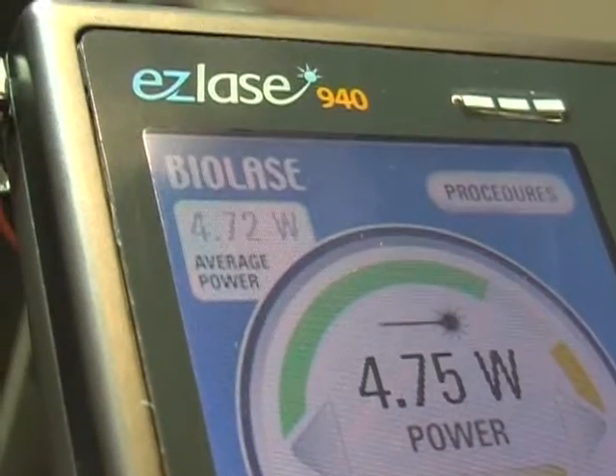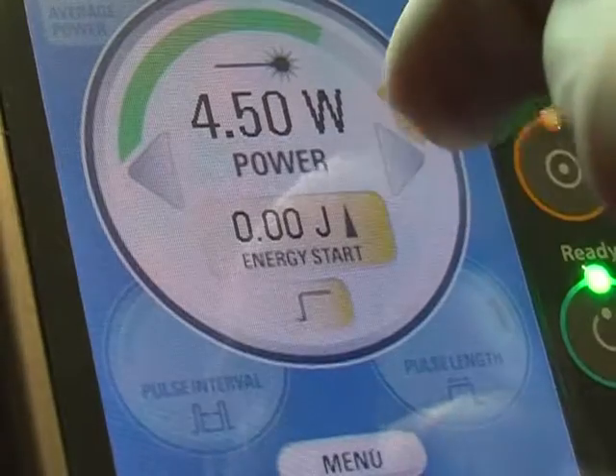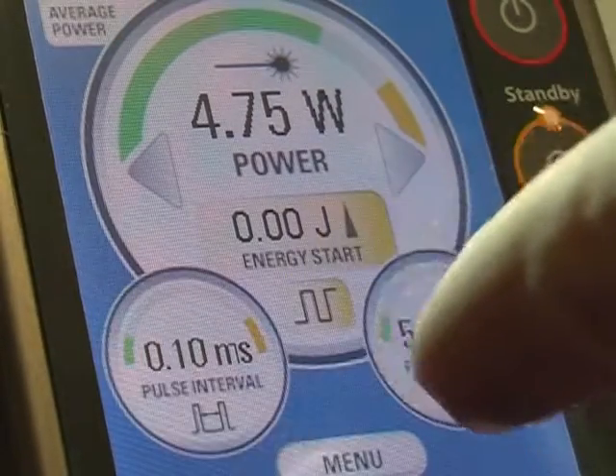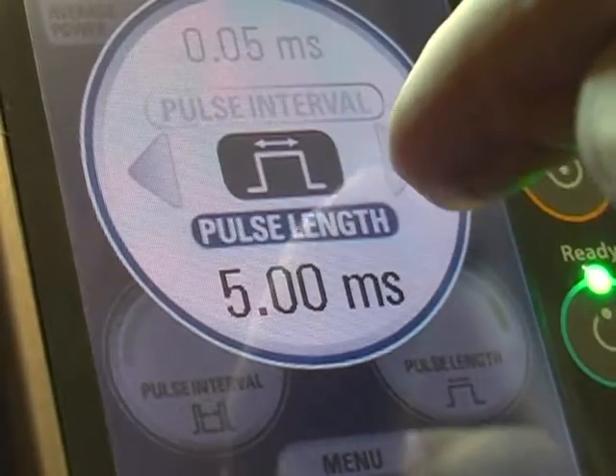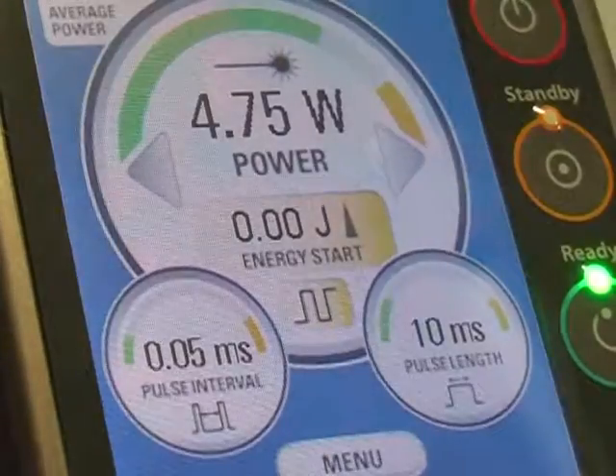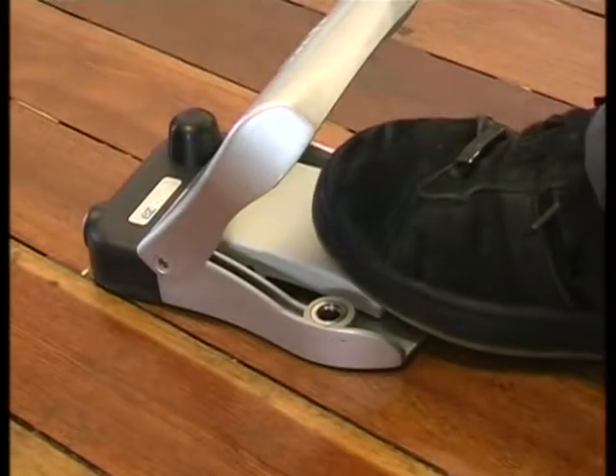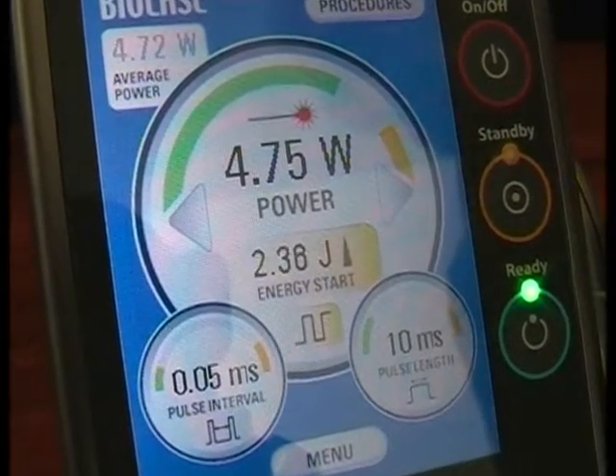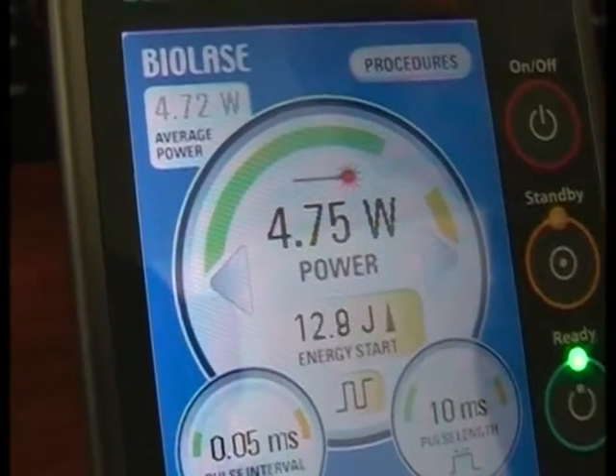In the top left of the screen, you will see the average power display. As you change the operating power, the pulse interval and the pulse length being used at any moment, the long-term average power being delivered to the patient becomes quite difficult to calculate. This simple feature continuously calculates and displays the average amount of power being transmitted to the tissue you are working on.